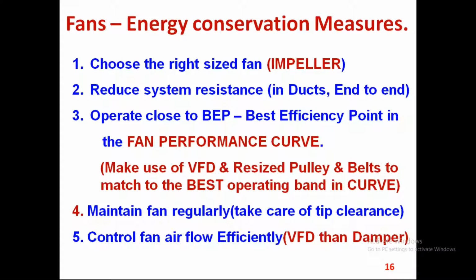So we are trying to operate the blower or the axial flow fan. The purpose is the same. The direction may be different, but the purpose is the same. The axial flow fan is also following the centrifugal aspects of the fan affinity laws, with a dead band. That is okay. But the best efficiency point of the fan performance curve can be achieved by putting the VFD and by resizing the pulley and belts. Automatically this is possible.